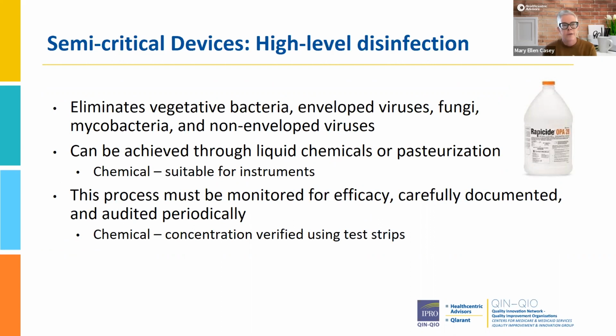High-level disinfection involves a lot of steps, and again, recognizing that a lot of facilities don't do high-level disinfection, you need to be aware that there are certain processes that have to be followed. We know that it eliminates vegetative bacteria and enveloped viruses as well as non-enveloped viruses. Most high-level disinfection that facilities see is achieved through liquid chemicals. Pasteurization is something that's done a lot with respiratory equipment and anesthesia equipment. So chemicals are typically suited for instruments.